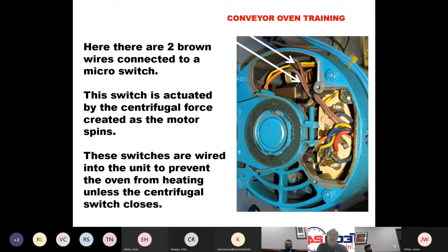On this motor, you see these two brown wires. These brown wires are connected to a micro switch. And this switch, called a centrifugal switch, is actuated by centrifugal force that's created when the motor spins. So these switches are wired into the unit to prevent the oven from heating unless these switches close. So on a direct drive blower, the centrifugal switch is the most common method of proving that we have rotation. They're always going to want to prove that there's rotation before they energize a heat circuit.